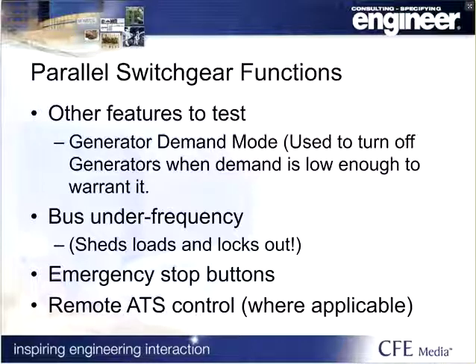Another feature to check out in the field is bus under frequency. It's important to know that the feature exists, because if the generator systems see a bus under frequency, they will drop all non-priority 1, non-life safety emergency loads, drop them all, and it will lock it out. That means in the middle of the night, somebody has to go there and unlock it to figure out what happened. The thought behind under frequency is that it is catastrophic at that point, and typically there's a 3-second delay for under frequency, and you can see it lock everything out. So in the field, it basically would be a little jumper across the under frequency. You watch all the switches shed, except for your priority 1, and know that this will work the way it's supposed to.